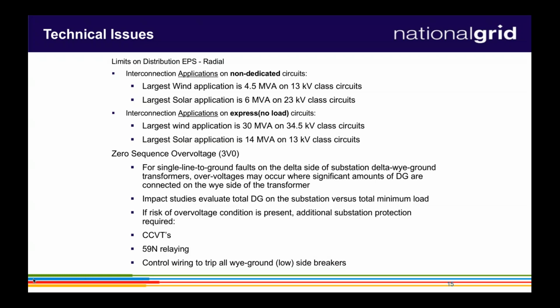We actually have instances where we have 20, 30 MVA substation transformers that are approaching their nameplate capacity on backfeed. We haven't yet, to my knowledge, upgraded one, but the thought of upgrading a substation transformer to allow more backfeed is definitely a sign of high penetration, and whether you try to spec a generation step-up transformer in that case. So interesting thoughts there of how you start dealing with this higher penetration.